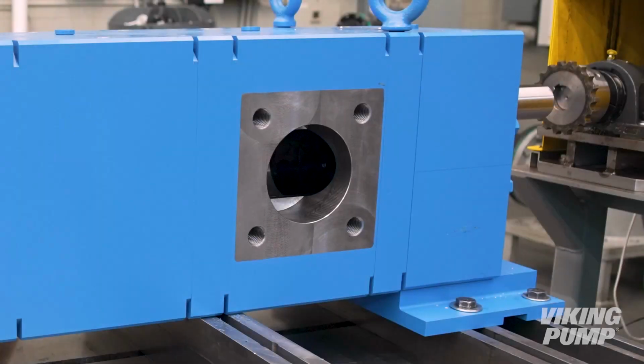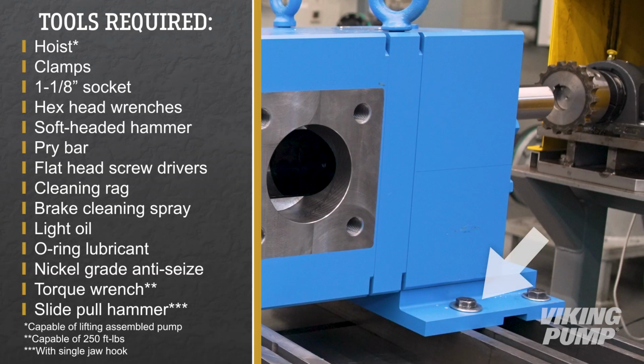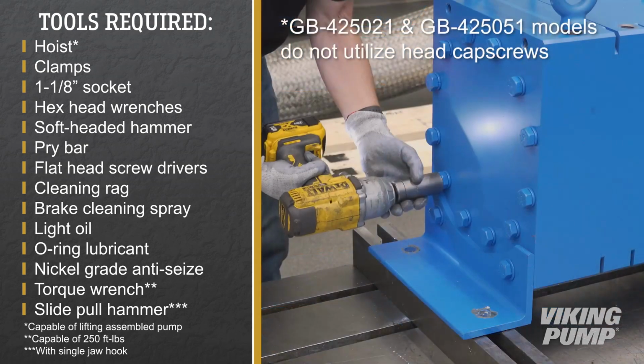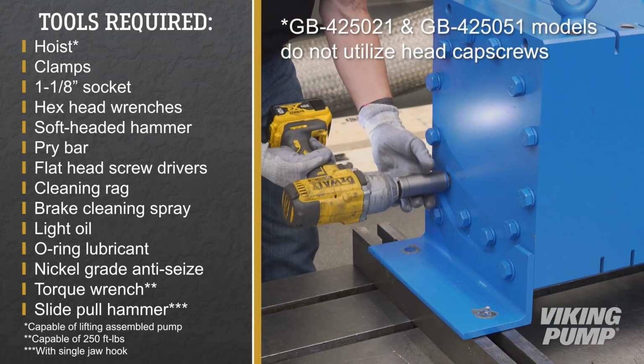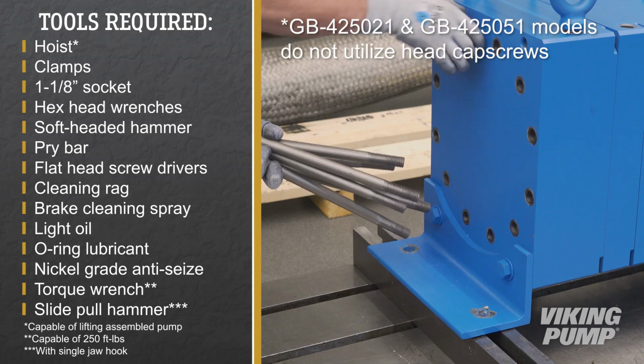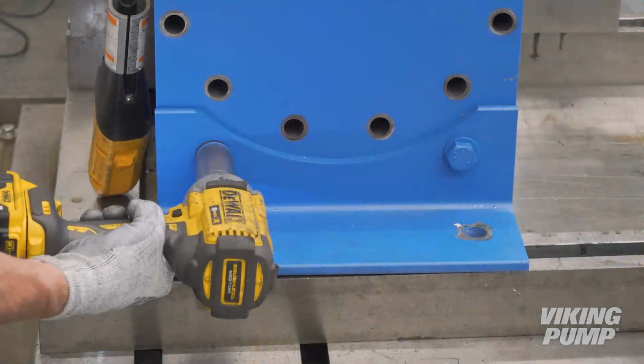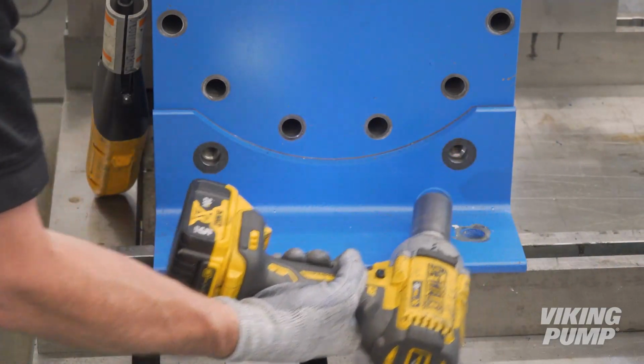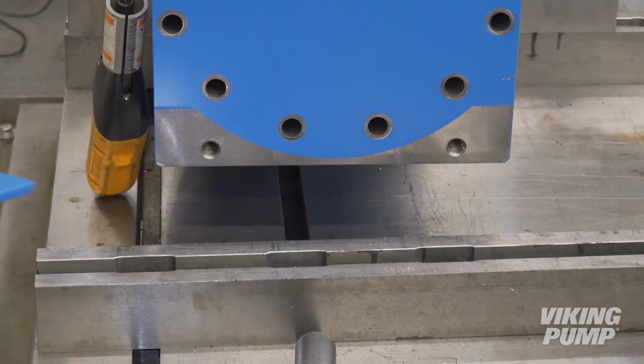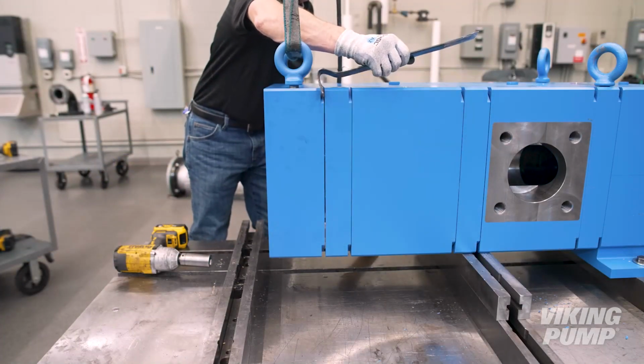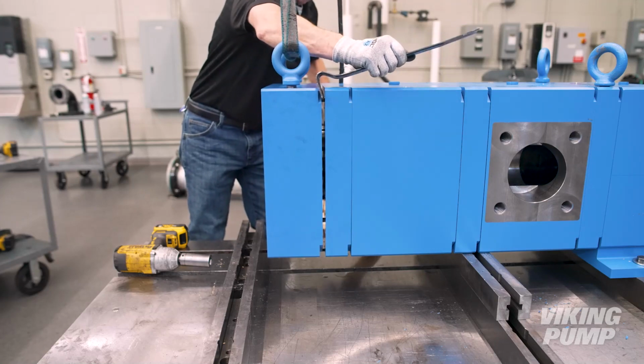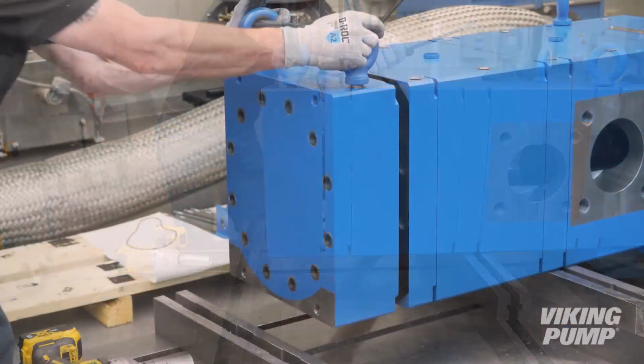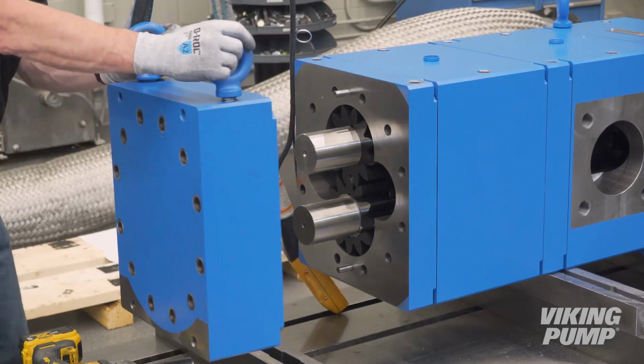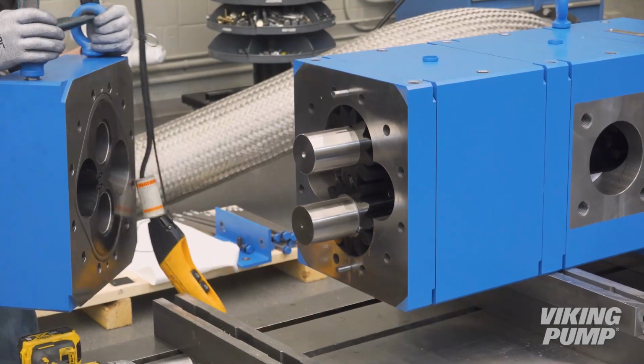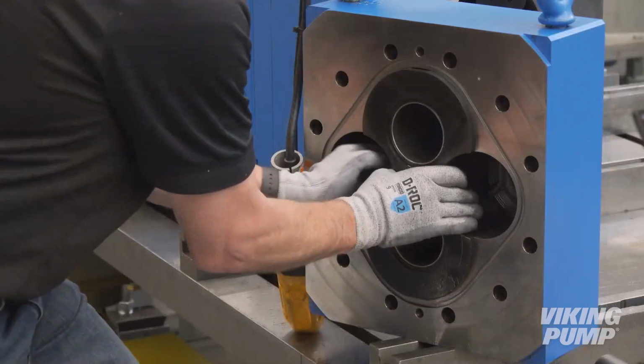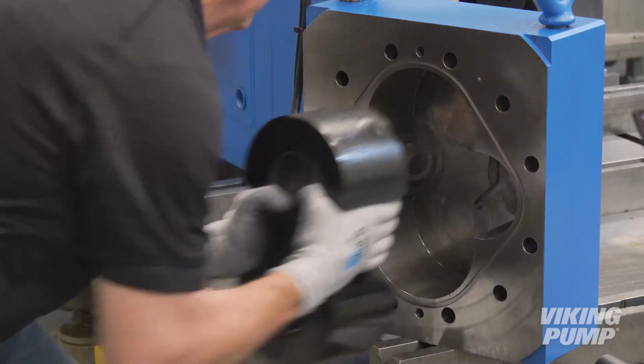To begin, make sure the pump is completely secured by bolting to the table or workbench. Loosen and remove the cap screws on the head end of the pump. Discard the cap screws. Remove the head mounting foot. Next, remove the head. A pry bar may be required. Be careful not to damage the face of this component. Set the pump head aside for reassembly. You may then remove and discard the bushing block and gasket and the head O-ring.